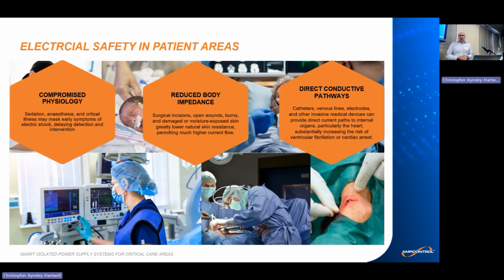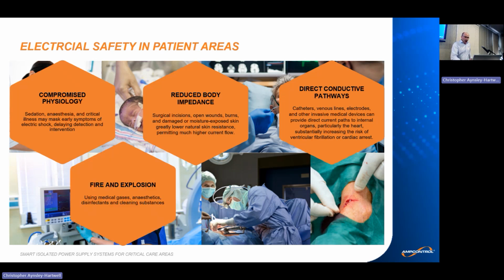Tubes, IV lines, and catheters can provide a direct pathway to internal organs, increasing the risk of, again, serious injuries or death, even from very small leakage current. And we shouldn't forget about medical gases, disinfectants, and other highly flammable substances commonly found in intensive care units, where an electrical fault can result in a spark or excessive heat, increasing the risk of fire or explosion.